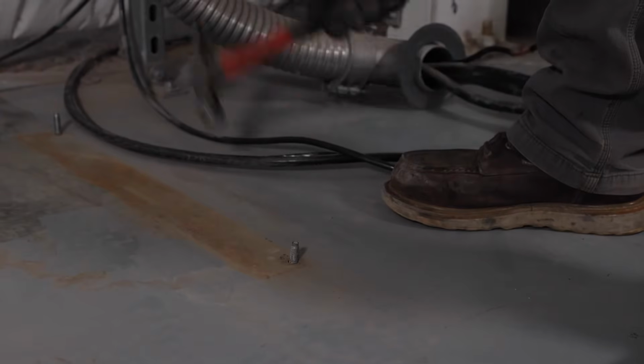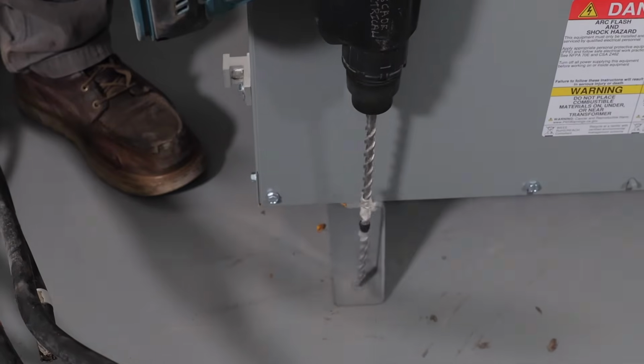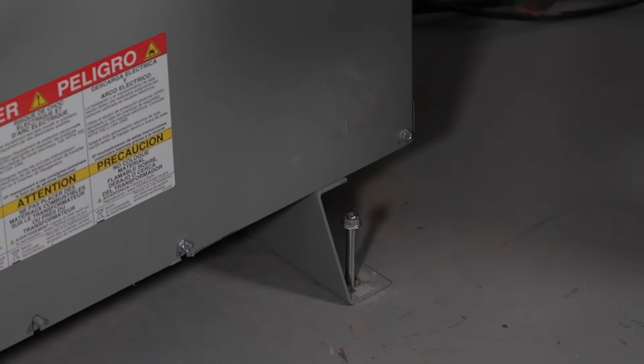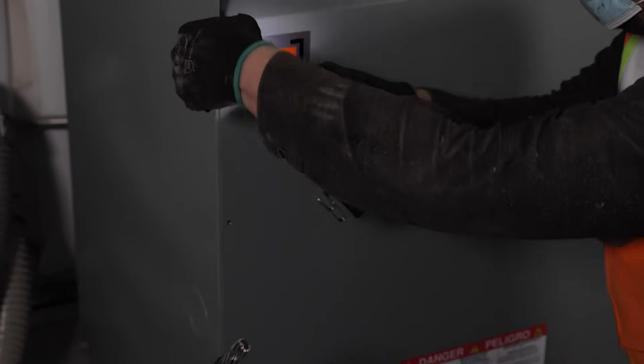Next, the transformer is anchored to the floor. In this example, we had to remove the old anchors entirely before installing the replacement. If the bolt holes in the transformer base are accessible from above, like with this new Maddox transformer, you can simply drill and sink anchors in place. The front panel from the new Maddox transformer is then removed.